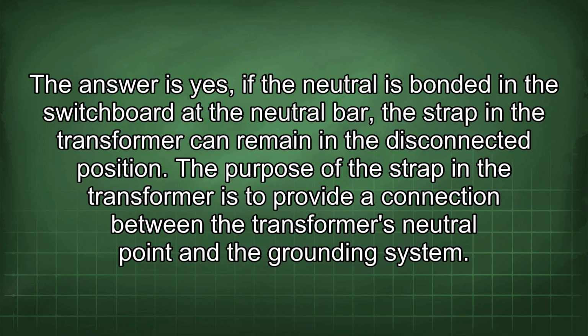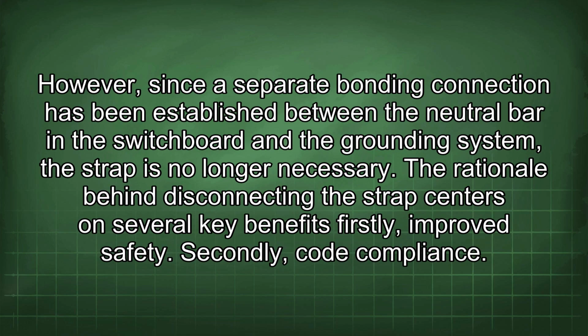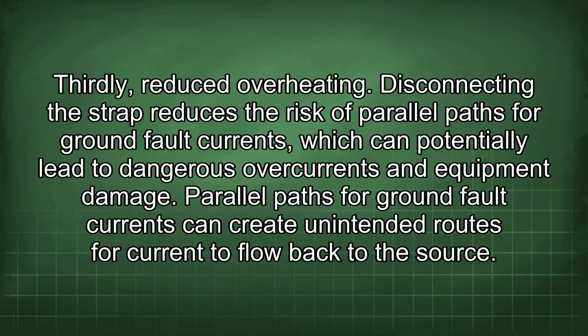The purpose of the strap in the transformer is to provide a connection between the transformer's neutral point and the grounding system. However, since a separate bonding connection has been established between the neutral bar in the switchboard and the grounding system, the strap is no longer necessary. The rationale behind disconnecting the strap centers on several key benefits. Firstly, improved safety. Secondly, code compliance. Thirdly, reduced overheating. Disconnecting the strap reduces the risk of parallel paths for ground fault currents, which can potentially lead to dangerous overcurrents and equipment damage.